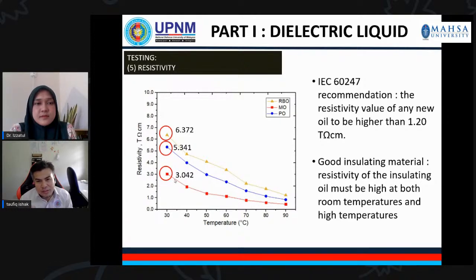So for a good insulating material or good insulating liquid, resistivity must perform not only at the low temperature, but also at the higher temperature as well. In this case, both of the vegetable oils perform very well at the lower temperature as well as the higher temperature. Inside the transformer, the temperature is around 60, can go up to 90, and sometimes can go up to more than 100 degrees. So the need for very good resistivity in the temperature range between 60 to 90 degrees is a very good advantage for transformer applications.